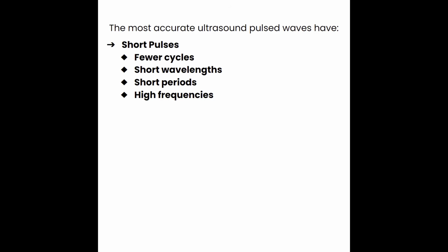I know we've discussed in earlier units that the use of a high-frequency transducer is better because it gives us more detail. Well, this list actually just kind of proves our point even further. Those high frequencies result in short wavelengths. Short wavelengths are going to make for shorter pulses, and shorter pulses are going to improve our axial resolution, which means we get more detail.